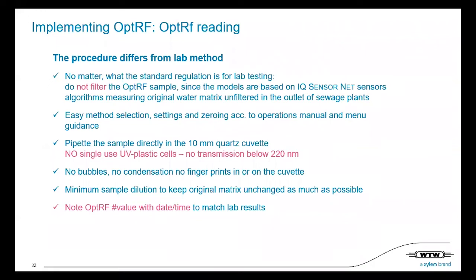We already said that the procedure differs a little from the lab with the optical reagent-free method. Do not filter the sample, because it's based on algorithms and the calibration curve is based on real samples. The real samples from IQ SensorNet are just open basins, rivers and waters, and there's usually no filtration done. Whereas for the lab method, filtration must be performed correctly.